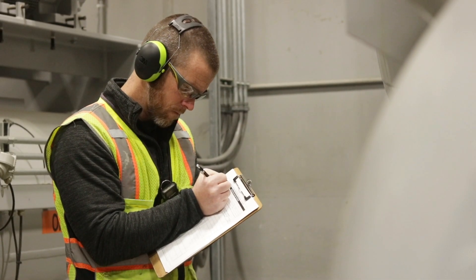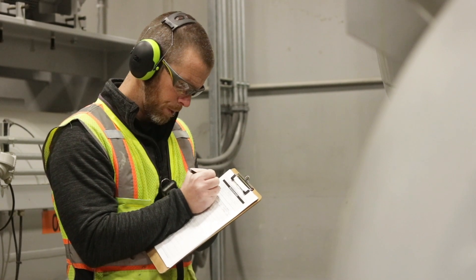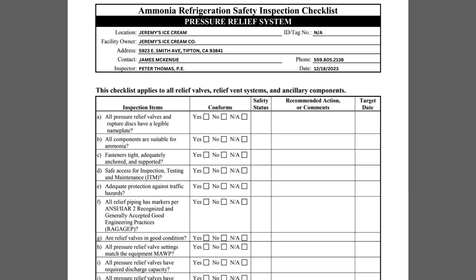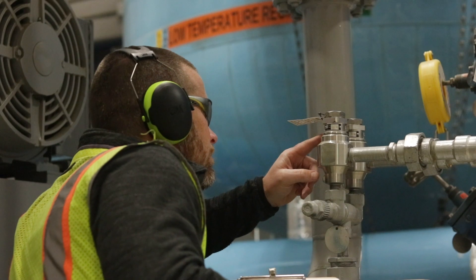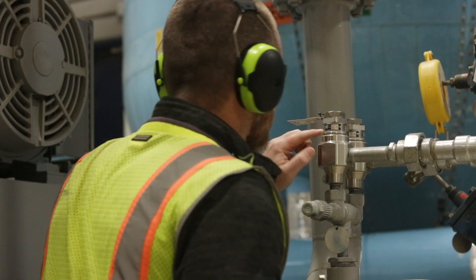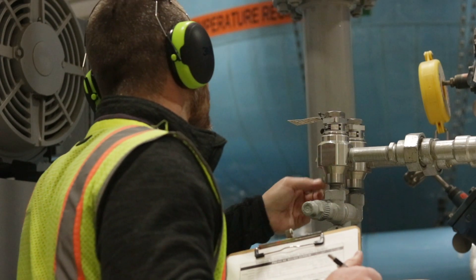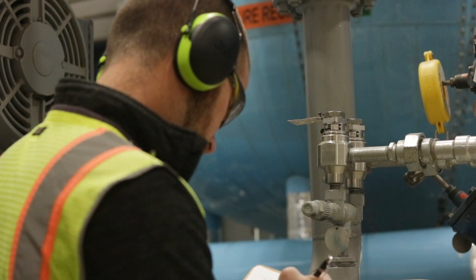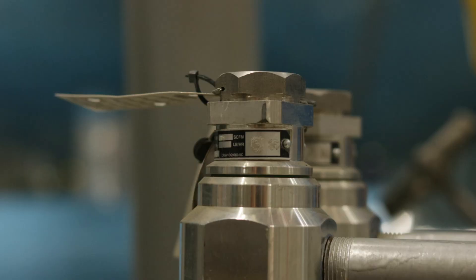Item A asks if all pressure relief valves and rupture discs have legible nameplates. Nameplates can be found on the body of the pressure relief valve and will contain information such as the manufacturer, model, set pressure, and certified capacity. Most importantly, the nameplate must have an ASME stamp and national board stamp.